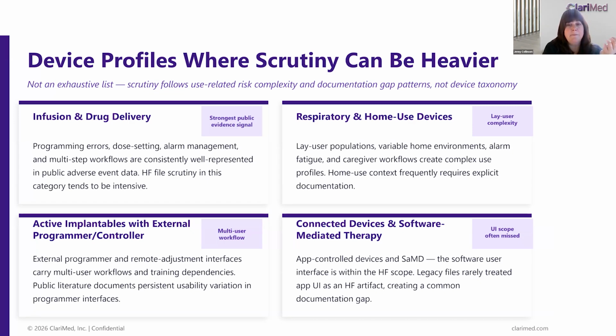connected devices, app-controlled devices, software as a medical device. The software is within human factors scope. I think with some of these legacy devices, though, apps were maybe developed as an afterthought. So the product was launched and then apps or guides were added, and documentation wasn't necessarily put in place as it should have been from a human factors point of view. But it's true that apps that have hazard-related use scenarios or critical tasks or contain information for safety are fully within the scope of human factors engineering, and therefore the gap would need to be filled for any submissions.